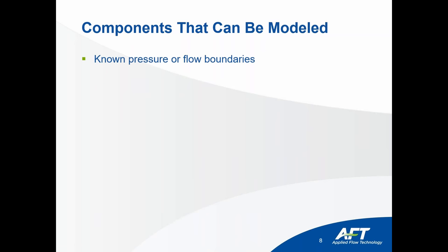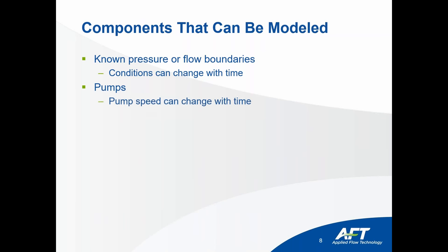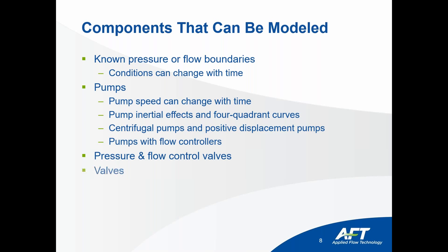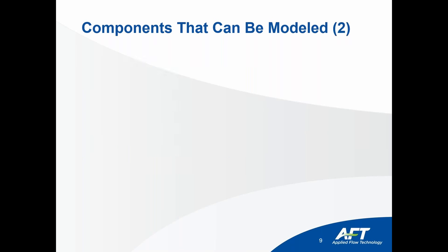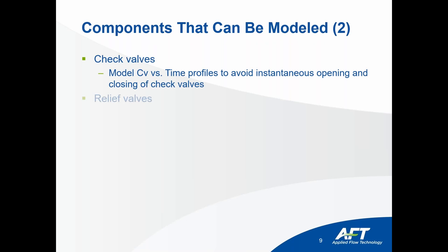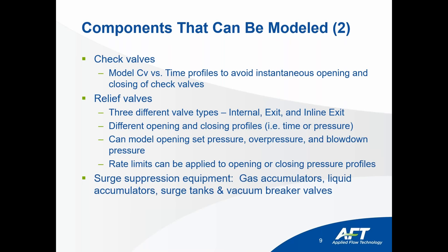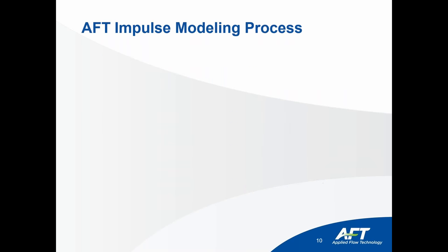Various components that can be modeled include pressure and flow boundaries that change over time, pumps accounting for inertial effects during pump starts or stops — both centrifugal and positive displacement pumps, pumps with flow controllers or VFDs, pressure and flow control valves, regular valves changing over time, check valves, relief valves, and different pieces of surge suppression equipment like gas accumulators, surge tanks, and vacuum breaker valves.